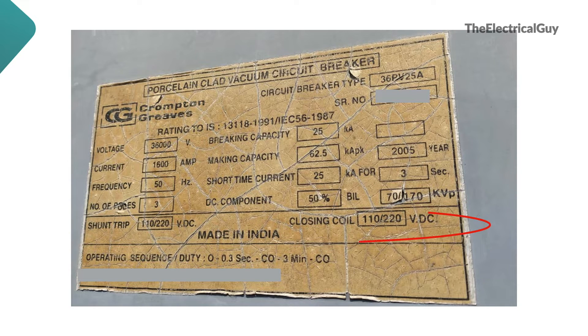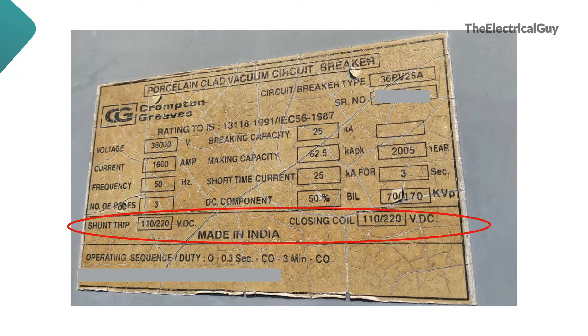Next, the voltage rating of the trip coil and closing coil is mentioned. The trip coil is also called a shunt trip coil. The voltage is generally DC voltage because the function of the closing coil and tripping coil is very important, and hence it needs a steady and constant supply, which can be provided by battery banks. This voltage is also called control voltage as it controls the opening and closing operation of the breaker. Generally it is either 110 V or 220 V DC — at least in India. It is a very rare case where dual control voltages are provided.